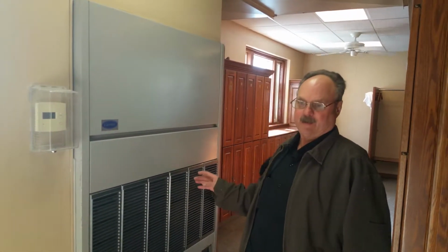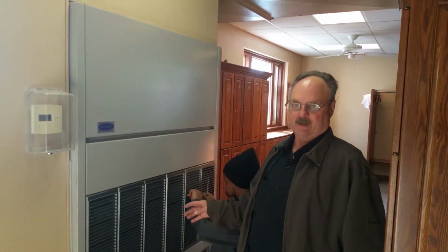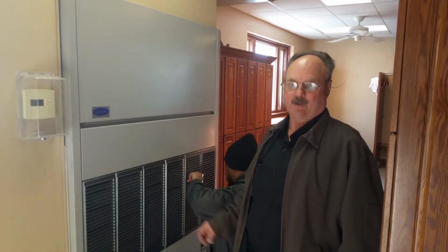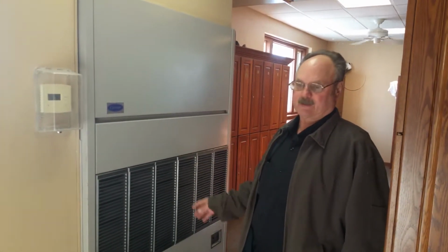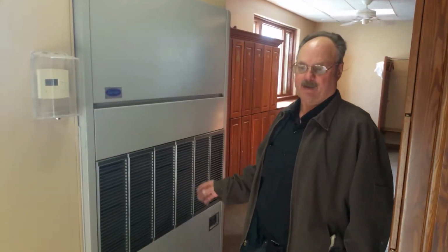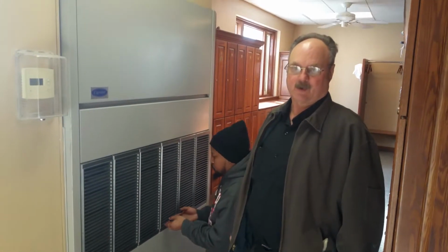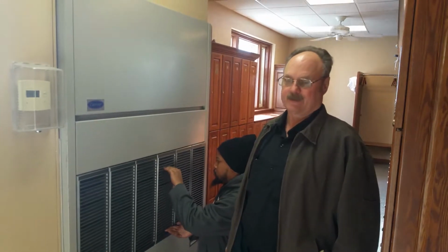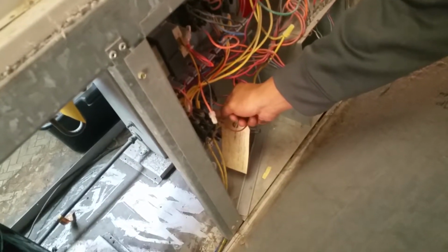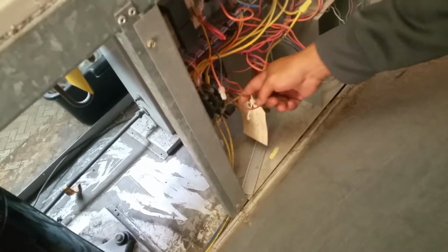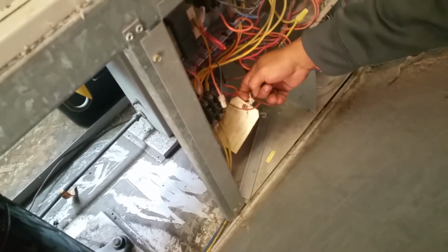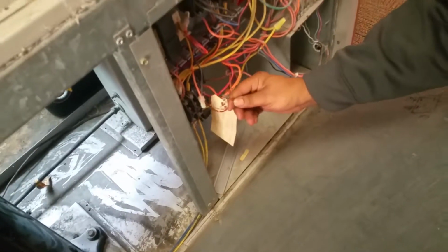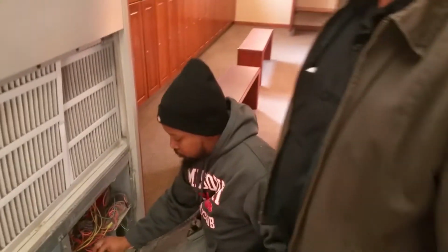What we're doing up here is the south locker room air conditioning unit is a water-cooled compressor which is tied into our cooling tower. So we're going to disconnect the relay that would put power on the compressor because it's a water-cooled compressor. What we're doing today is disconnecting the power to the compressor, and Chris is going to disconnect it off the relay that starts the compressor. What color is what? The brown with the tag. Okay. Just pull it off there, Chris.